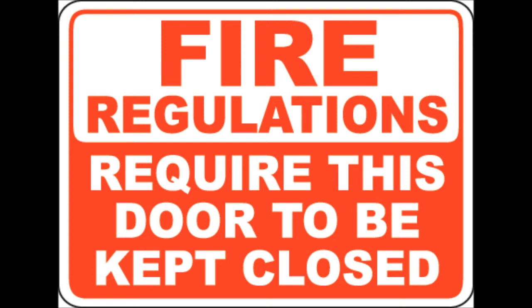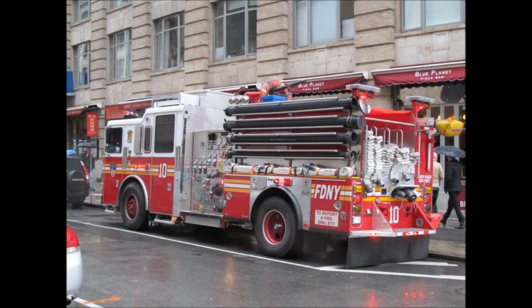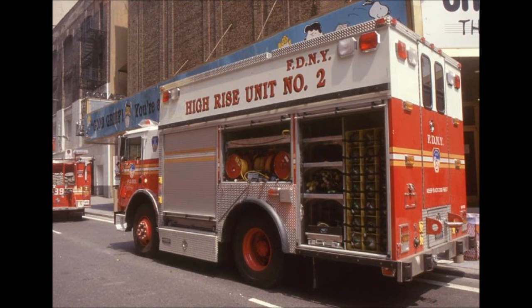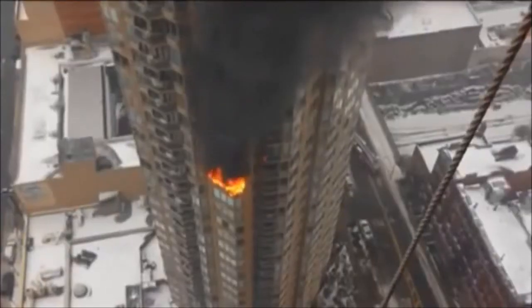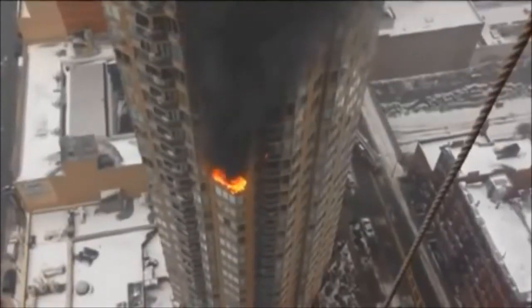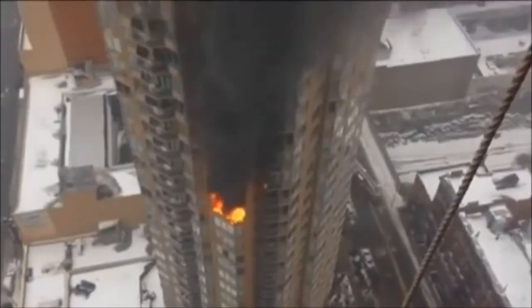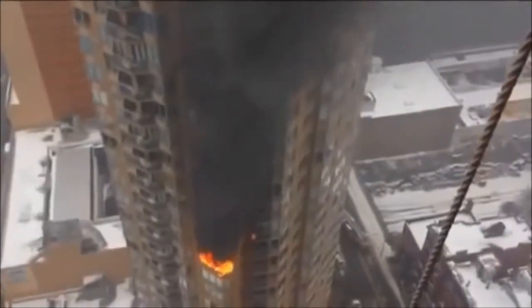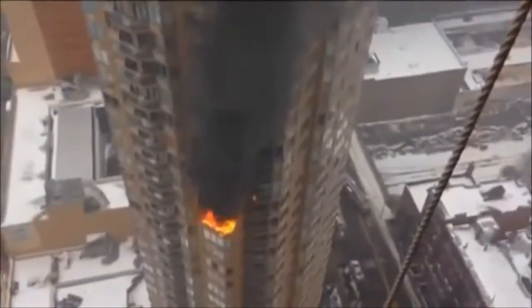Looking globally, the application of these concepts allow for safer construction of buildings. With towering skyscrapers, firefighters have to determine how to get water from the ground to the 100th floor of a skyscraper in case of an emergency. The FDNY, Fire Department of New York, has to purchase special engines they call high-rise engines, which contain enhanced pumpers capable of pumping water up to the standpipe systems of large buildings so firefighters can access a secure water supply hundreds of feet above the ground.